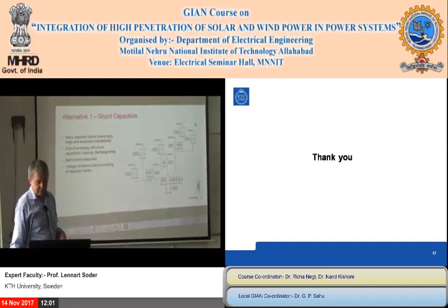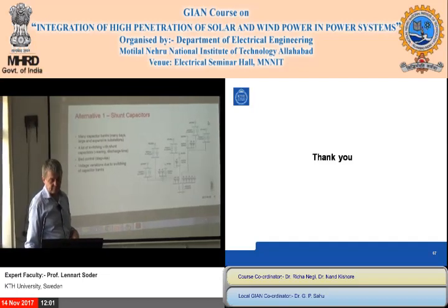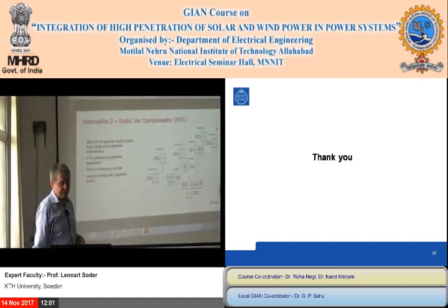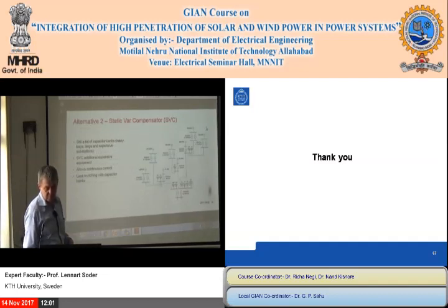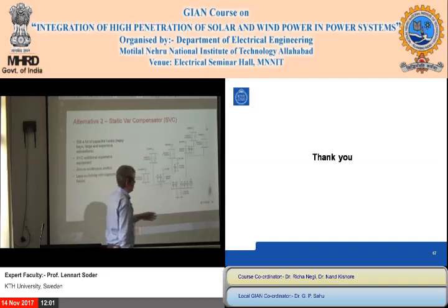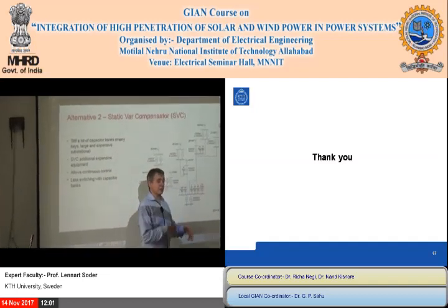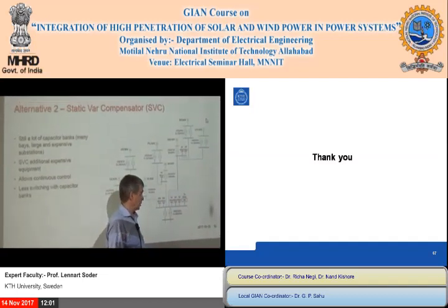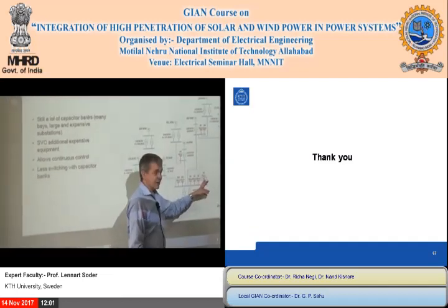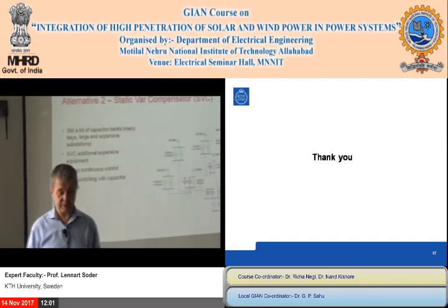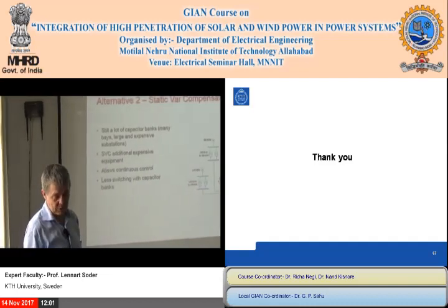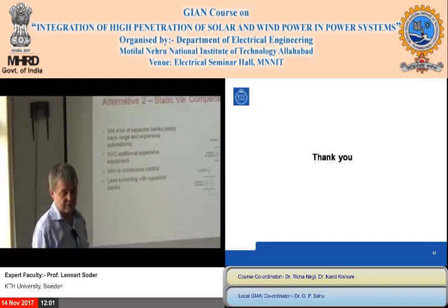An alternative is, of course, to have SVC, static var compensation, which means that you have power electronics switches for all these power capacitors and so on. This is nice, but expensive. That is how it looks. You get less switching and, of course, continuous control and this kind of thing.